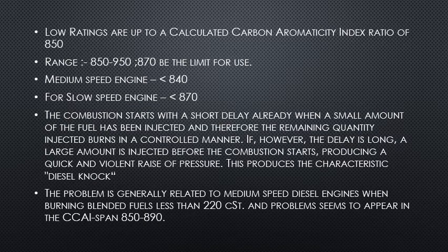Lower ratings are up to a value of 850. However, the range is 850 to 950, in which 870 is the limit of use, above which the fuel is unusable. We cannot use that fuel in the diesel engines. So for the medium speed engines, it should be less than 840. For the slow speed engines, it should be less than 870.